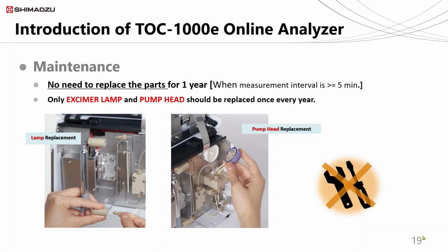TOC-1000e unit doesn't need to replace parts for 1 year when the measurement cycle is 5 minutes or higher. This is a 1 year maintenance-free instrument. It may vary depending on the sample properties and measurement conditions. Only the lamp and pump head need to be replaced every year, and it can be done by hand. No need to use any tool during replacement. Also, it can be done by users.